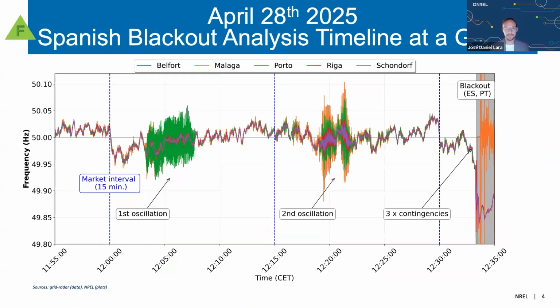First, let's take a wide view of the timeline of the event. These changes you see here, we've highlighted where the market intervals happen. So when you see changes in the frequency in this plot, we can identify when there are contingencies versus when there are actually market events. Around noon, from the data we have, there's a first oscillation that happened. Then there was a second oscillation, and shortly after, several of the contingencies started to go through.